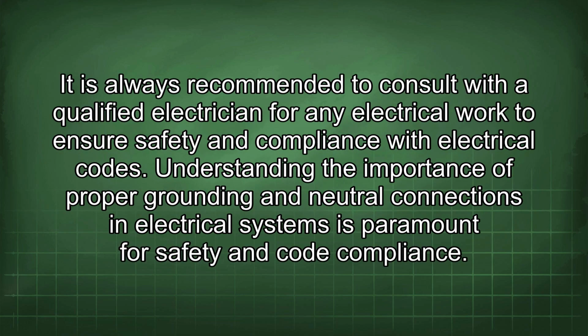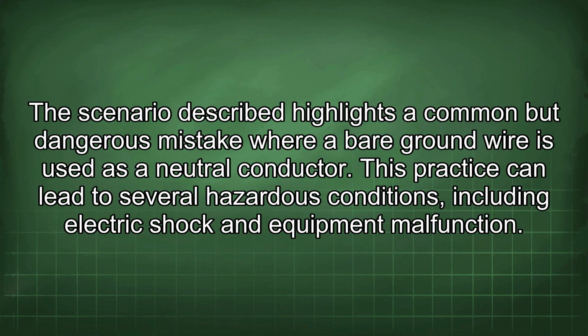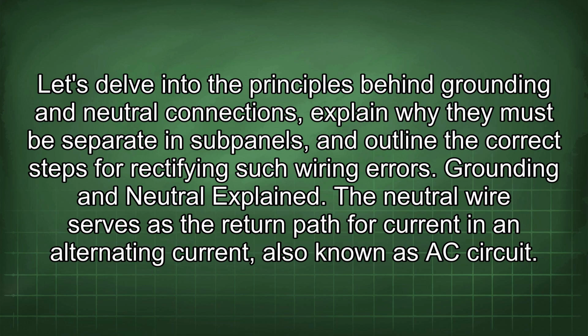It is always recommended to consult with a qualified electrician for any electrical work to ensure safety and compliance with electrical codes. Understanding the importance of proper grounding and neutral connections in electrical systems is paramount for safety and code compliance. The scenario described highlights a common but dangerous mistake where a bare ground wire is used as a neutral conductor. This practice can lead to several hazardous conditions, including electric shock and equipment malfunction. Let's delve into the principles behind grounding and neutral connections, explain why they must be separate in subpanels, and outline the correct steps for rectifying such wiring errors.